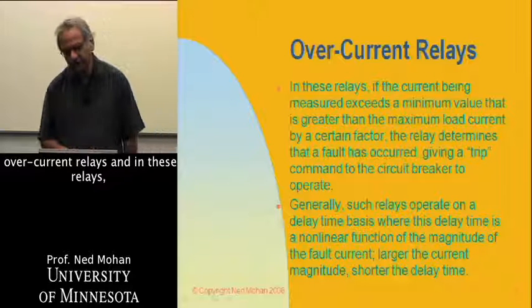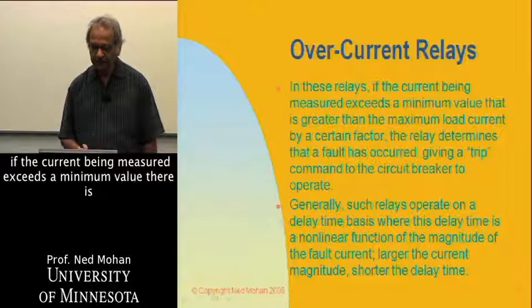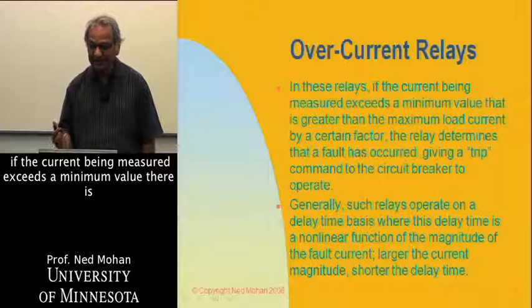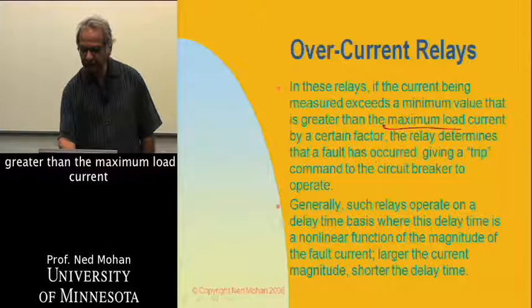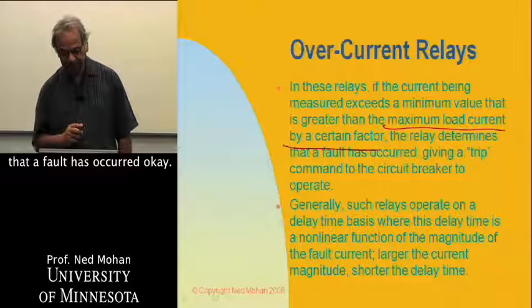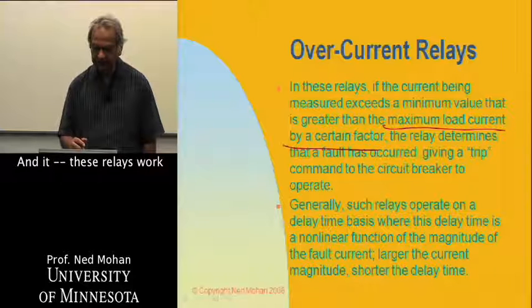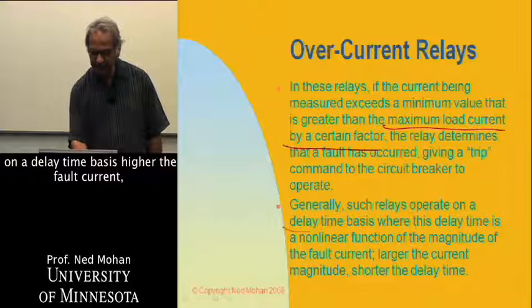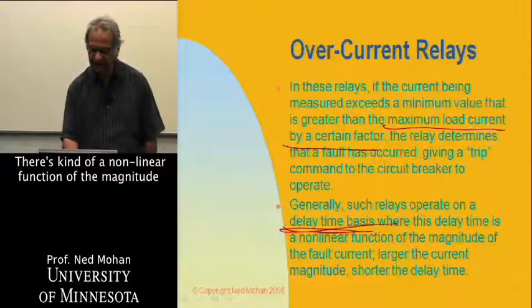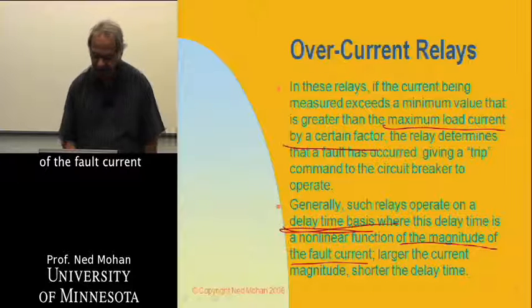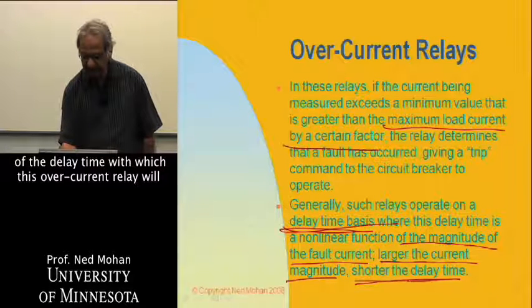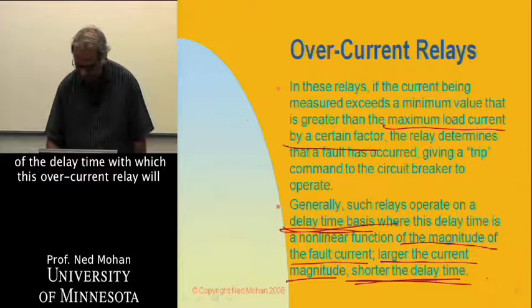Then we have overcurrent relays. In these relays, if the current being measured exceeds the minimum value — which is greater than the maximum load current by a certain factor — then the relay determines that a fault has occurred. These relays work on a delay time basis: the higher the fault current, the faster it will operate. It is a nonlinear function of the fault current magnitude, meaning a larger current magnitude results in a shorter delay time.